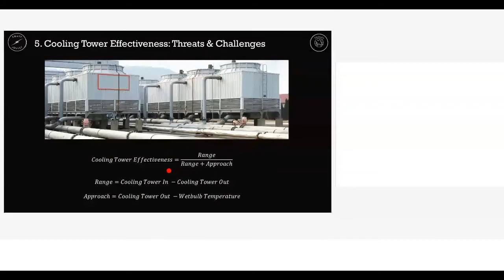These are the formulas for the effectiveness the company is trying to achieve, that is the delta T between these two, water coming in and water going out, that is the range of the cooling tower. The difference between the water going out and the ambient wet bulb temperature is the cooling tower approach. So range divided by range plus approach gives the CT effectiveness, or cooling tower effectiveness, which should be somewhere around 70-72% for ideal centralized AC operation. Anyway, that's what I believe is written here.